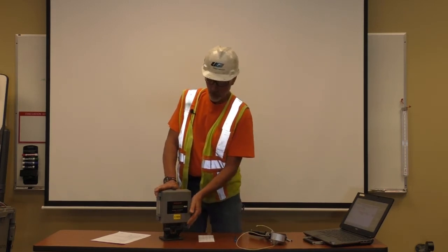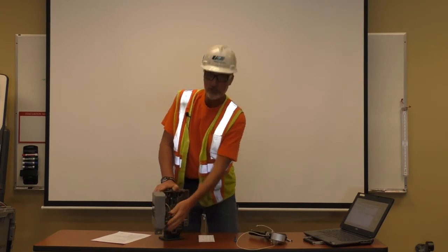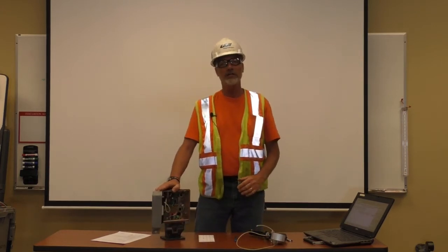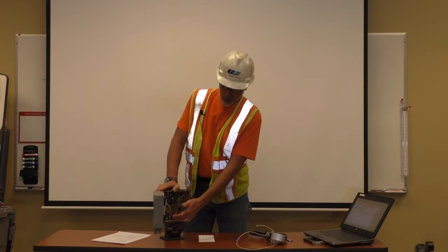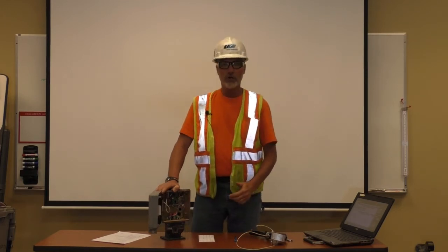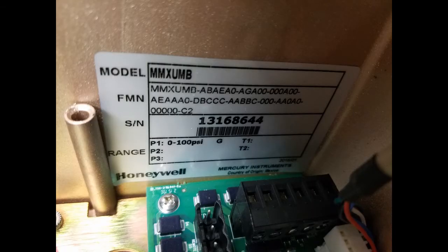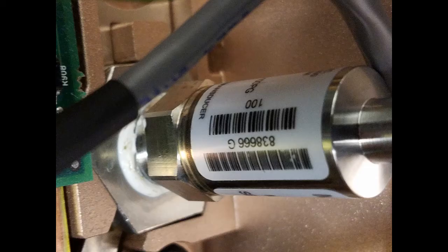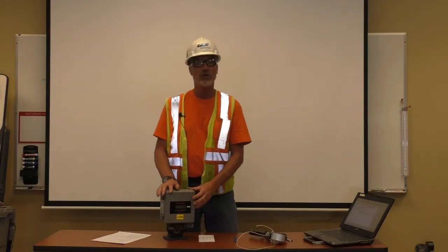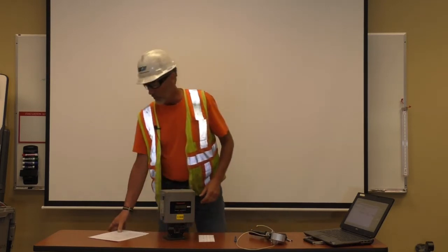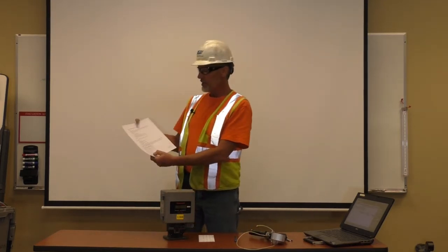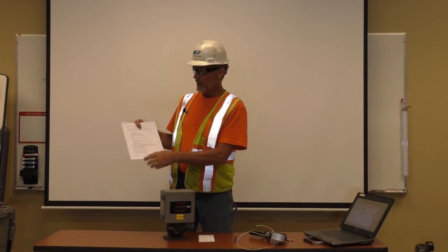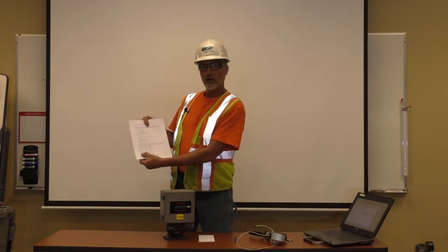First thing you want to check is what transducer pressure that your device has. This particular one is a 0 to 100. You can check that by either checking the label on the inside or on the transducer itself. We have devices out there that are 0 to 15, 0 to 100, 0 to 300, 0 to 600, and 0 to 1500. So this one is a 0 to 100.